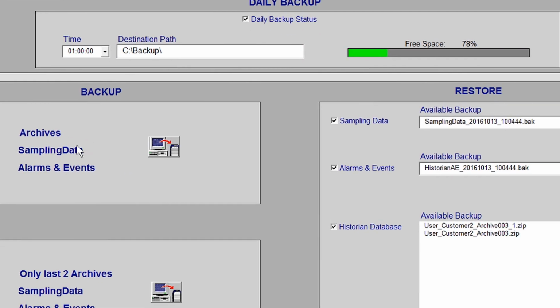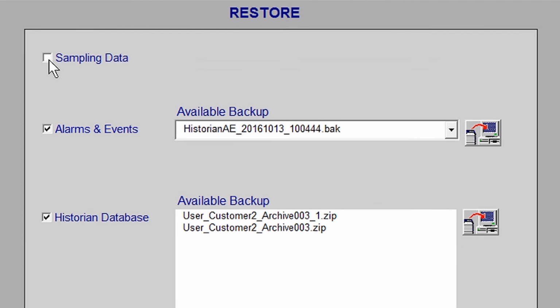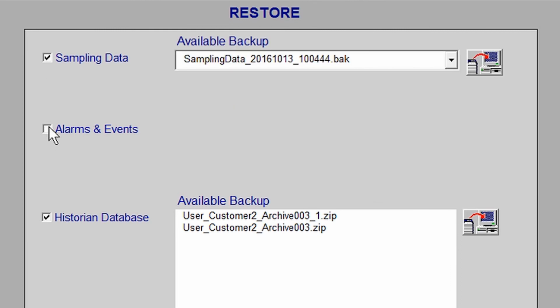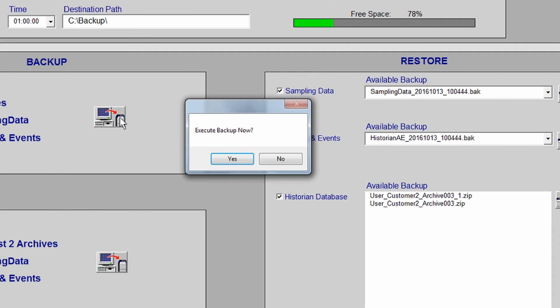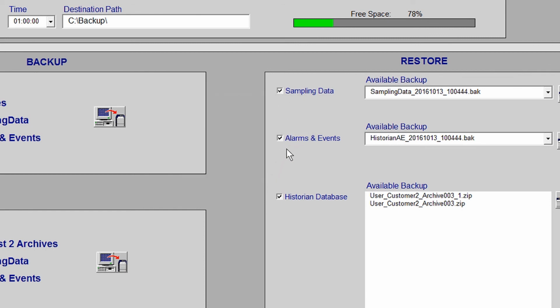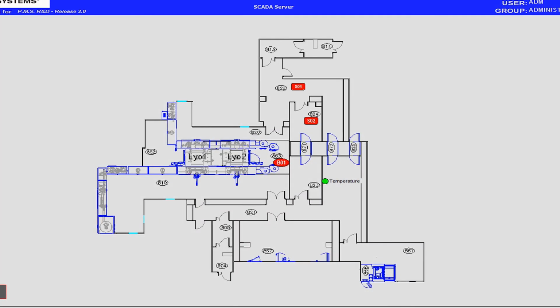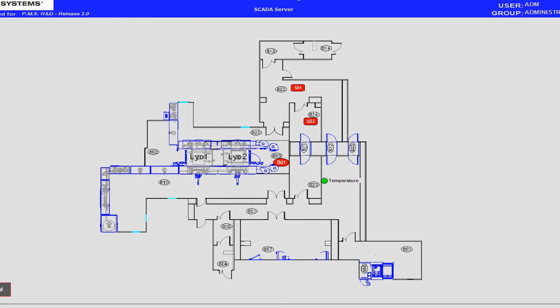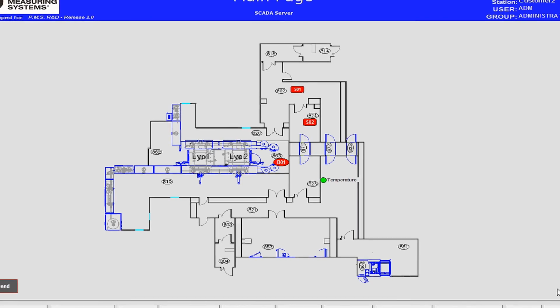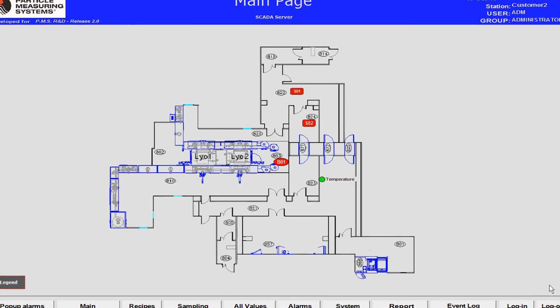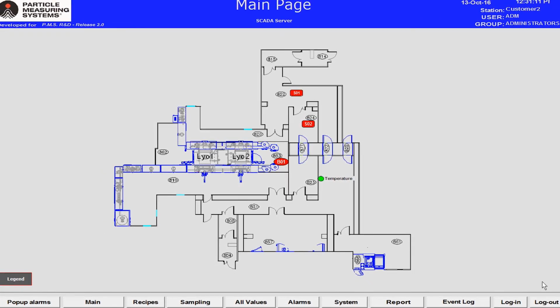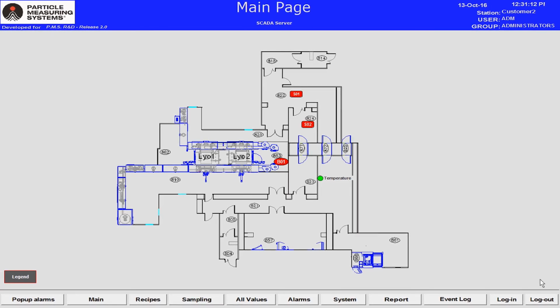The sampling data is stored separately from the alarm and events. System backup can be manually initiated for each item separately. If it is necessary to restore the system, sampling data can be restored separately from alarm and events. The user interface is a critical part of any SCADA-based system, allowing for the easy collection of data as well as providing reports that provide valuable data for proper operation of a controlled environment for the manufacturing of products.